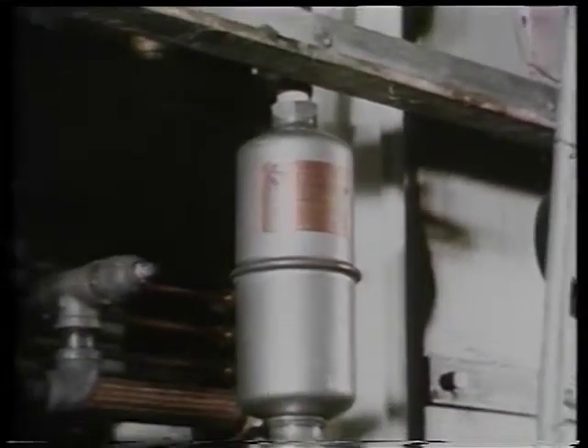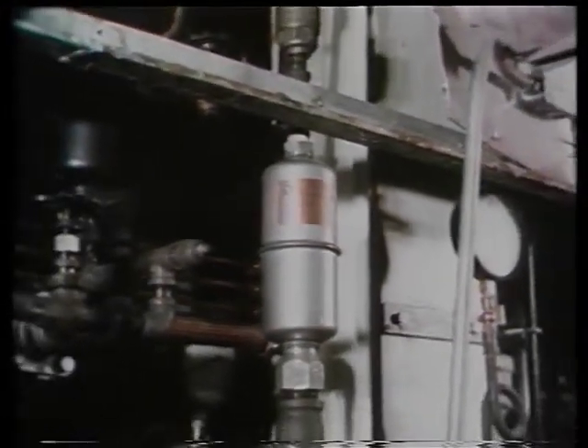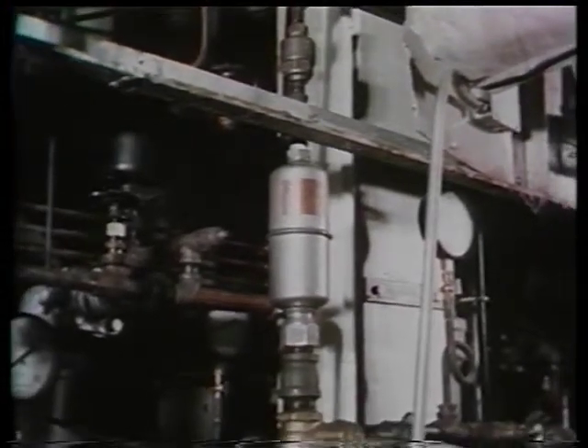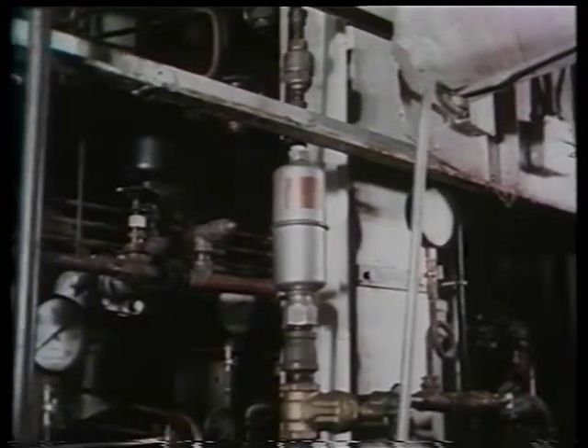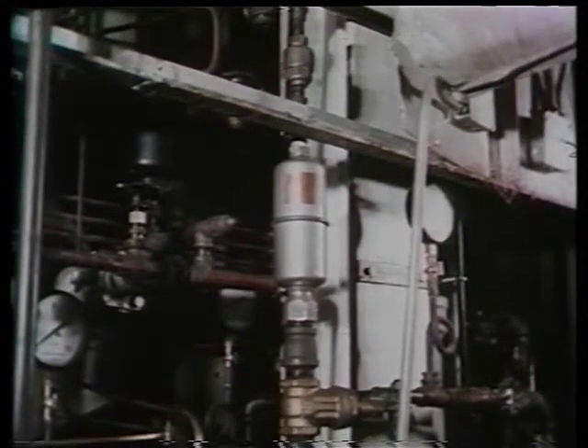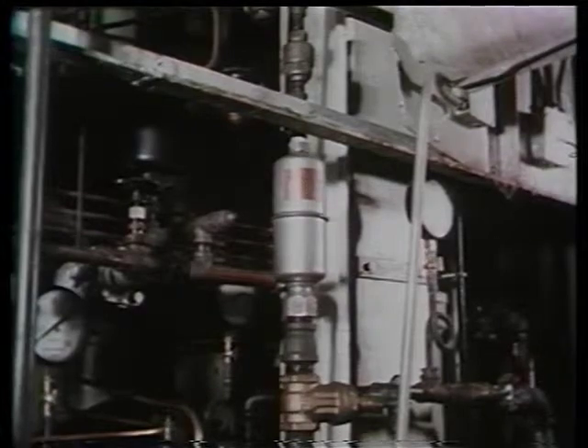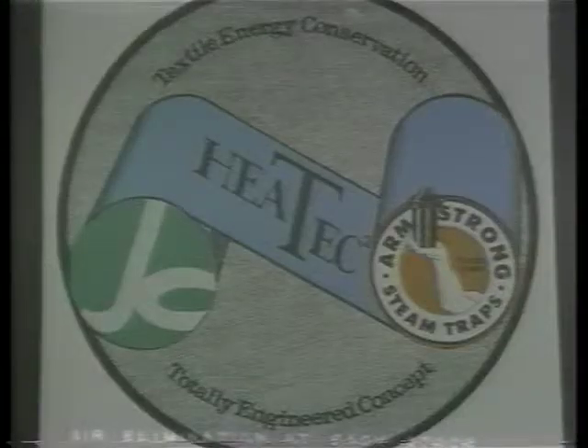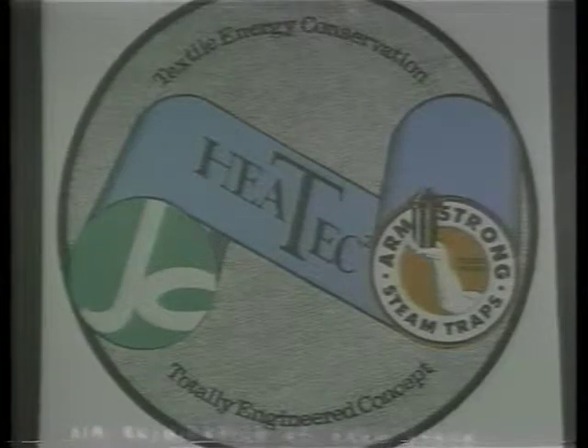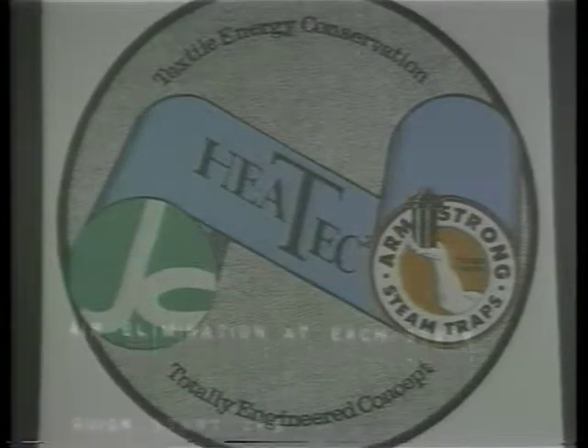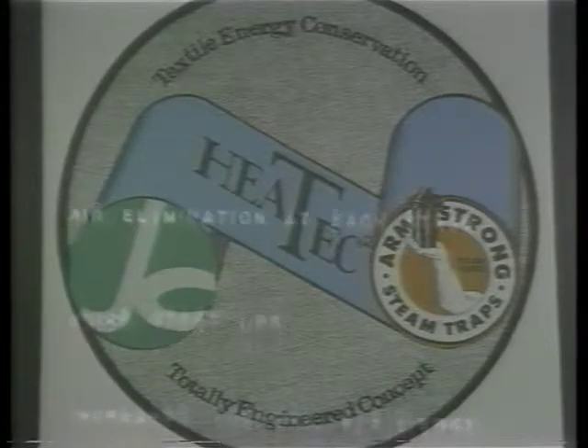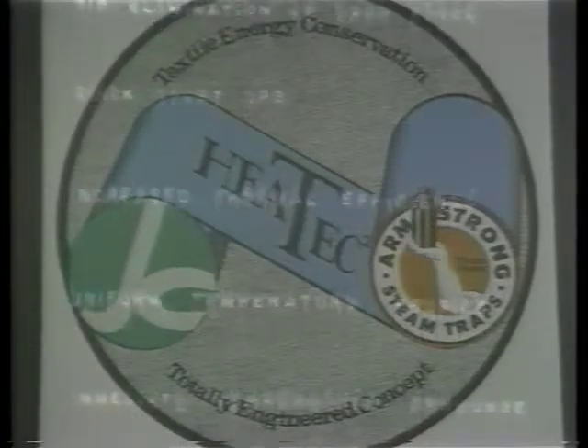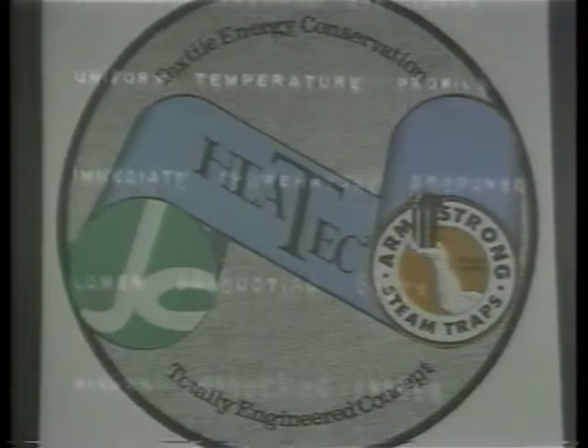The air eliminator senses the temperature depression caused by the presence of non-condensable gases such as air. It automatically opens a valve to discharge the air from the system. When the air has been removed, the valve automatically closes, avoiding the loss of steam. The HeaTec system will provide these advantages over the conventional trap and stationary siphon system: air elimination at each stack, quick startups, increased thermal efficiency, uniform temperature profile, immediate temperature response, lower production costs, and higher production speeds.